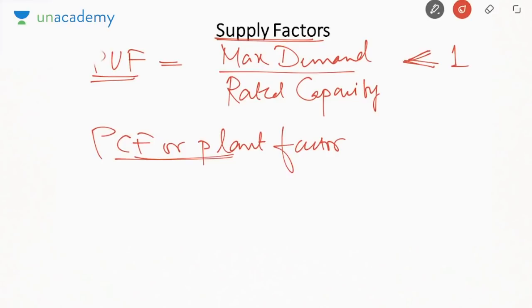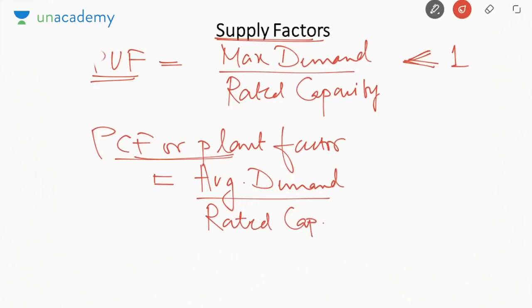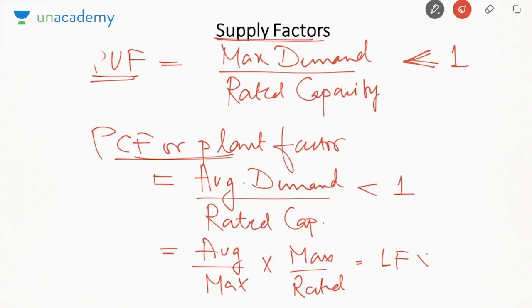Whenever we are talking about plant factor, you must remember it is the plant capacity factor. It is equal to average demand by rated capacity, that is, how much is the average demand throughout the day and how much is your rated capacity. This will also be less than 1, because if maximum demand is less than rated, the average will always be less than rated. We can express it like this also: average by max into max by rated. Average by max is load factor, into plant utilization factor. So this can also be expressed in this form.